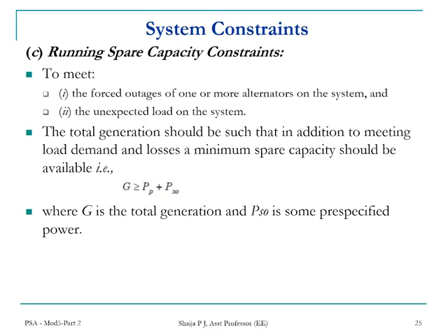Therefore, to meet the contingencies, the capacity of units online, that is running, must have a definite margin over the load requirements at all times. This margin, which is known as the running spare capacity margin, or the spinning reserve, ensures continuity by meeting the load demand up to a certain extent, given the probable loss of generation capacity.